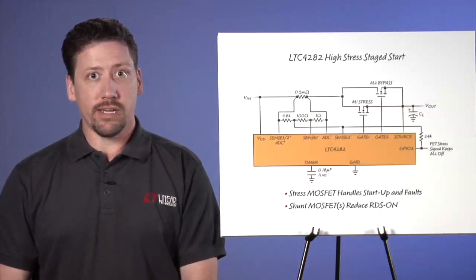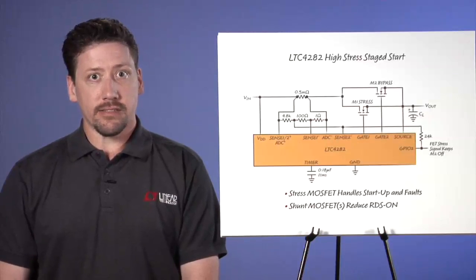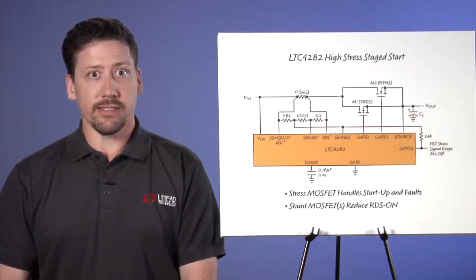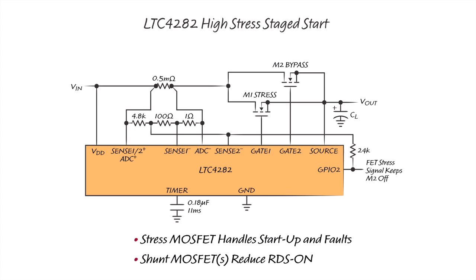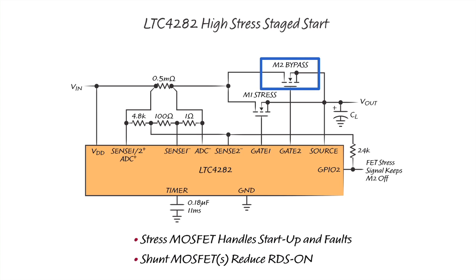The second staged application we call high stress staged start. This configuration benefits applications where loads consume significant DC power while inrush is occurring, or for systems that must operate through significant input voltage steps without generating a fault. Such input voltage steps occur when redundant supplies are connected or disconnected from the input power rail. In this configuration, the stress MOSFET has a large SOA that can start the load at full power. Once the output is up and the stress MOSFET's gate is fully enhanced, one or more inexpensive low-RDS(on) bypass MOSFETs are turned on to reduce power consumption in the MOSFETs to a reasonable level. The bypass MOSFETs are turned off whenever current limiting occurs in order to divert power dissipation to the high-SOA stress MOSFET.